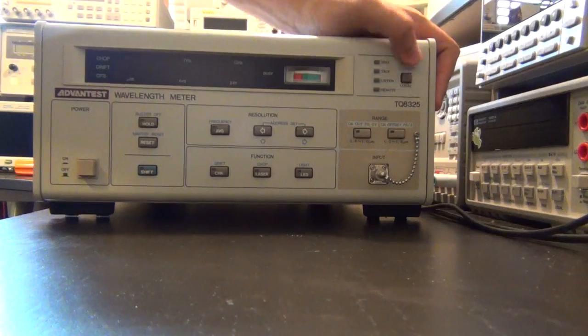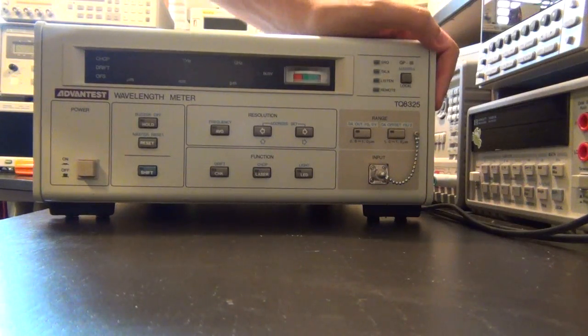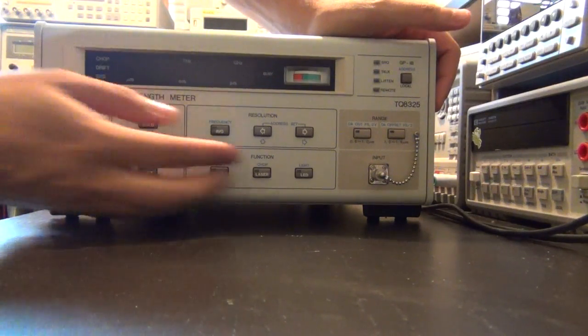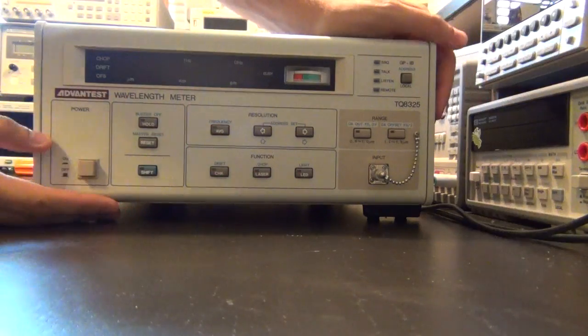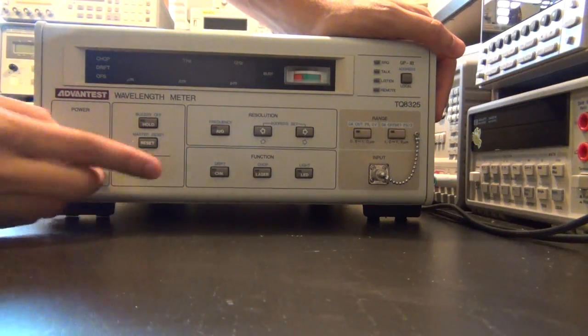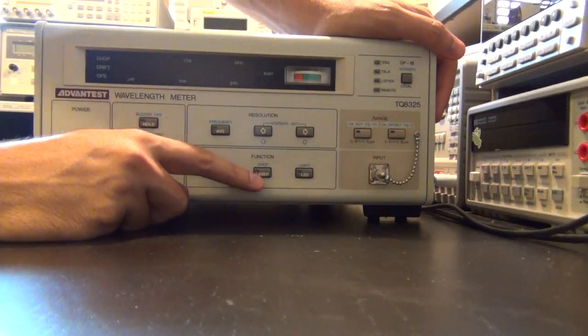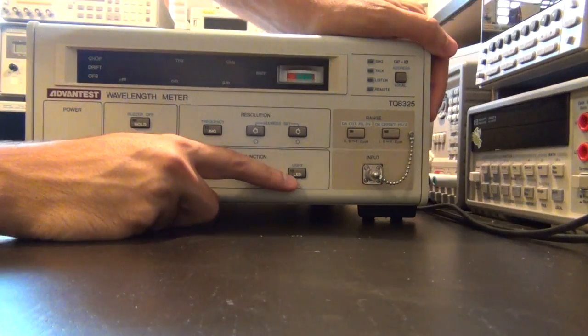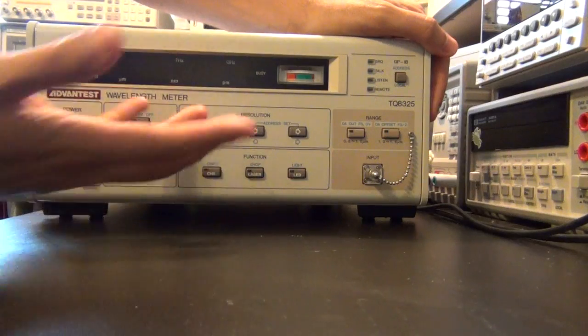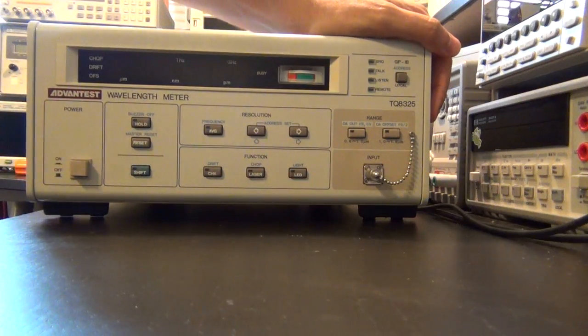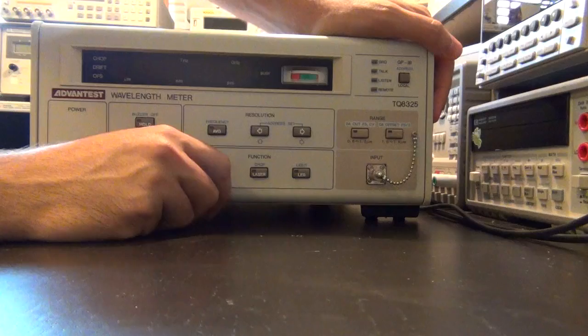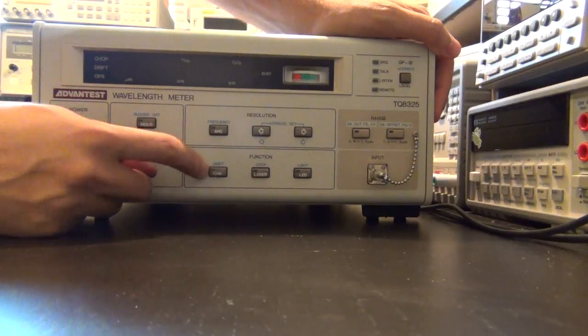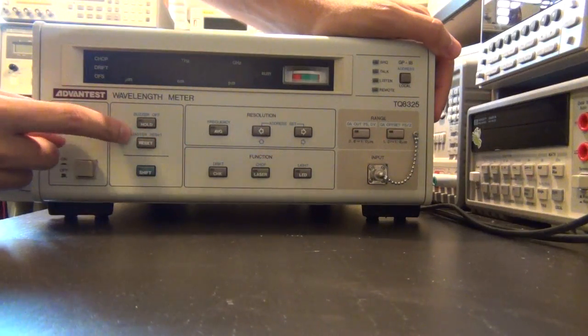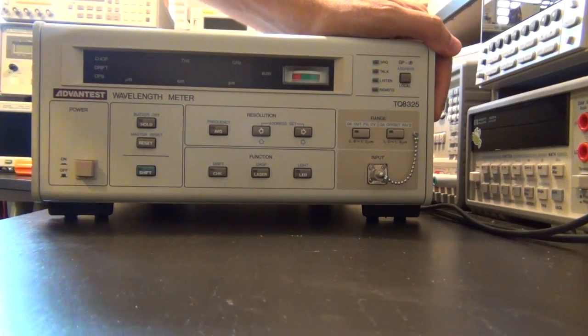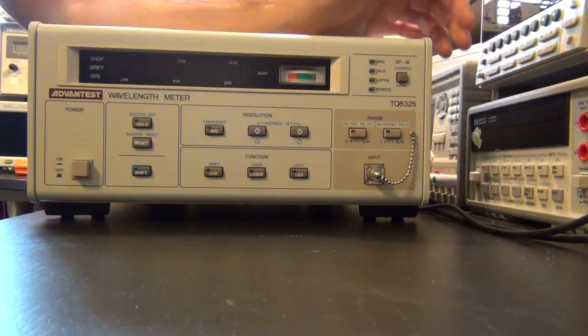It also has a GPIB port, so it has some LEDs and lights and the address select for the GPIB. But the rest of the buttons are really simple. It only does one thing. It measures wavelength. And so it can measure the wavelength of a coherent source like a laser, or perhaps the wavelength of an LED source that's not so monochromatic, not so pure, so you lose some resolution when you select the LED. But it also has a built-in self-test. If you do a master reset, it does its own calibration. You can average things out, you can do some chopping. So it really is very simple on the outside.